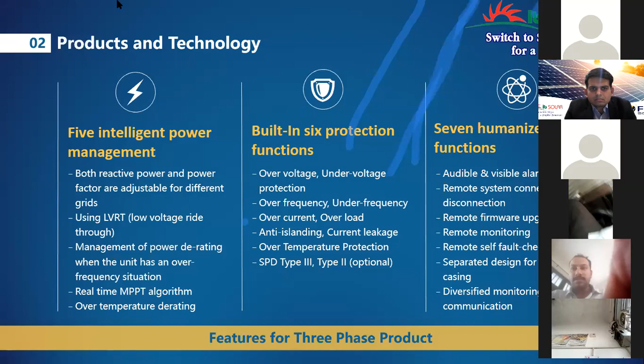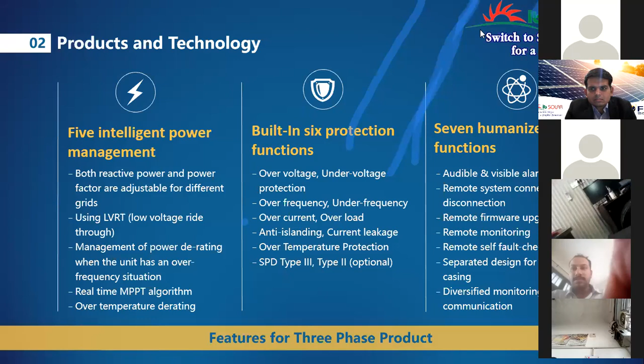Another is that the inverter has 6 types of inbuilt protections: over voltage protection, under voltage protection, over frequency and under frequency protection, over current and overload protection, over temperature protection, and ground fault indication protection. These are all the protections needed in the inverter to operate in different grid conditions, load conditions, and temperature conditions. Also, the inverter has humanized functions that we can easily observe, like audible and visible alarms during a ground fault, remote monitoring and firmware upgrade, and a separate design for the upper and lower casing of the housing in the 20 kilowatt to 70 kilowatt inverters. Next.